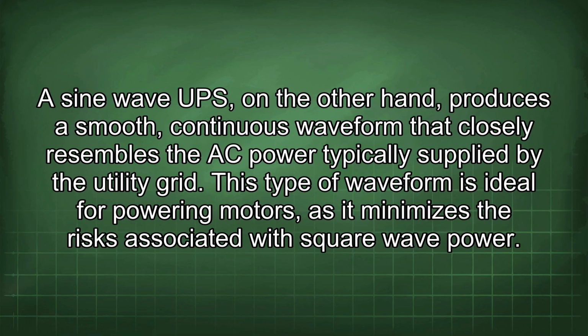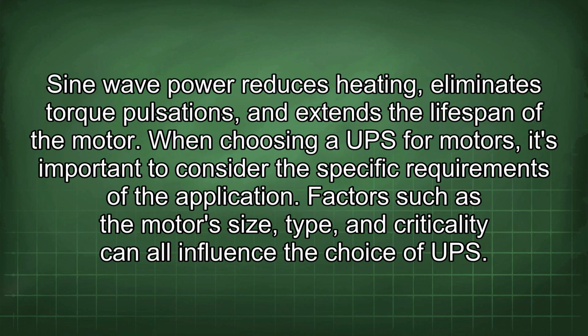A sine wave UPS, on the other hand, produces a smooth, continuous waveform that closely resembles the AC power typically supplied by the utility grid. This type of waveform is ideal for powering motors, as it minimizes the risks associated with square wave power. Sine wave power reduces heating, eliminates torque pulsations, and extends the lifespan of the motor.